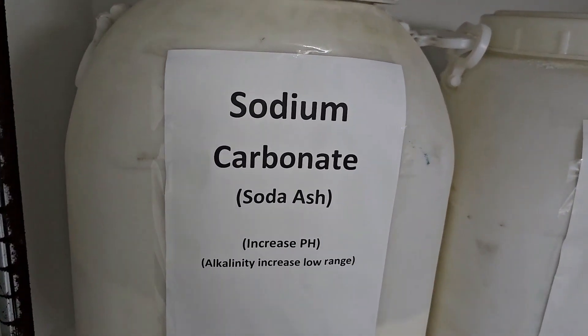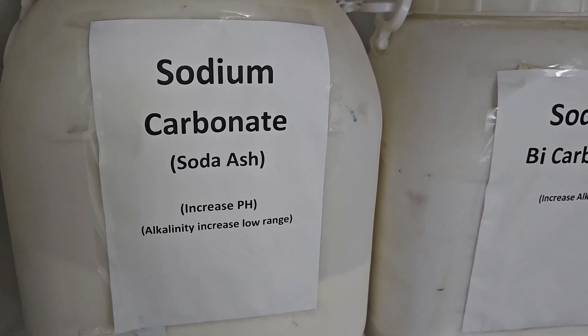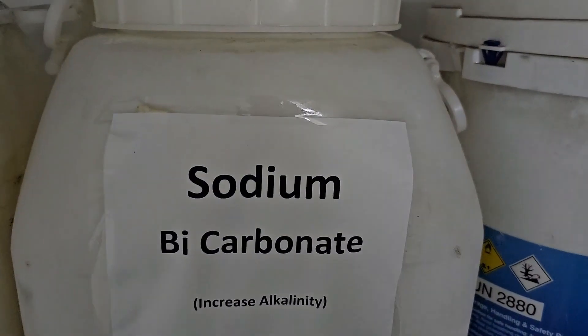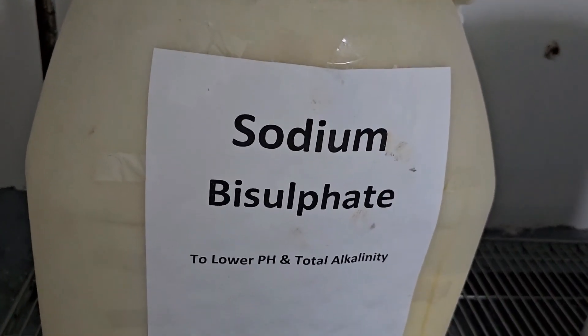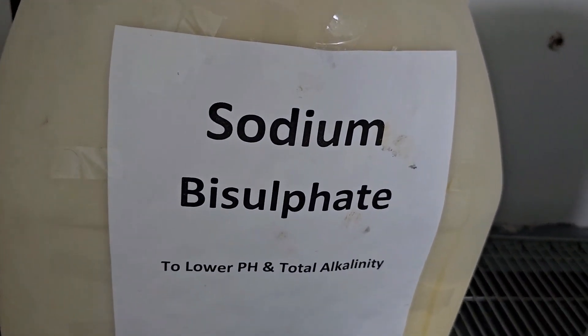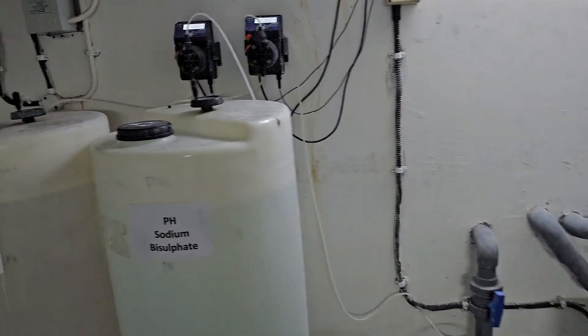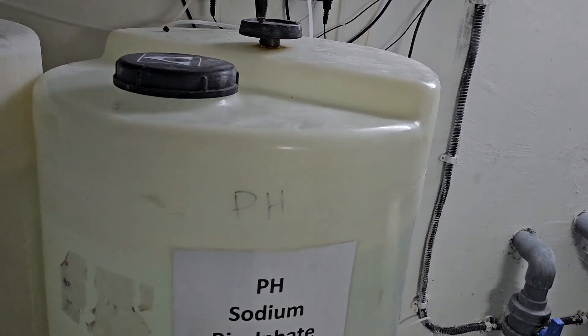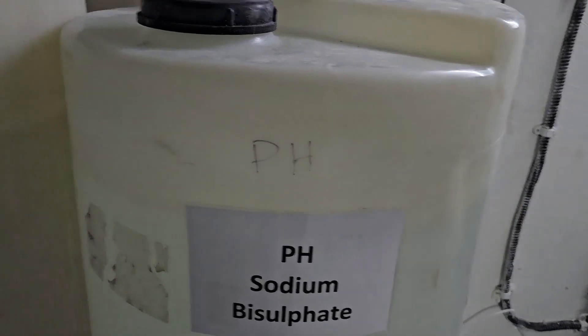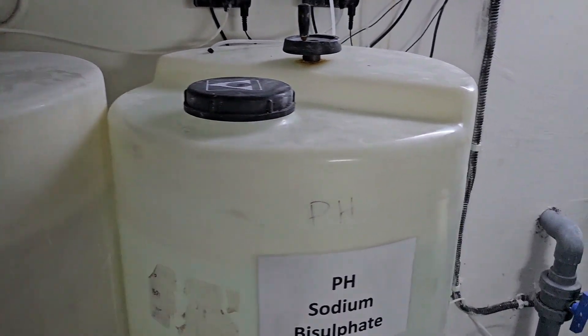Here are the chemicals. This is sodium carbonate — also called soda ash in common language — used to increase pH. This is also sodium bicarbonate, which increases alkalinity. This one is sodium bisulfate, used to reduce pH, which we use in the auto chemical dosing tank. And this is chlorine — we are using it to maintain chlorine levels.